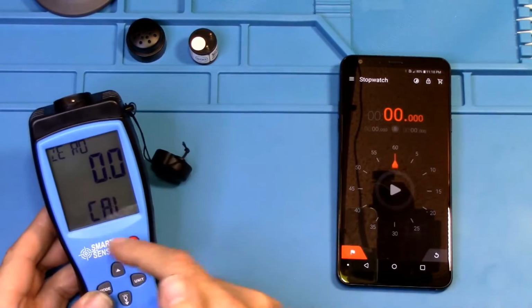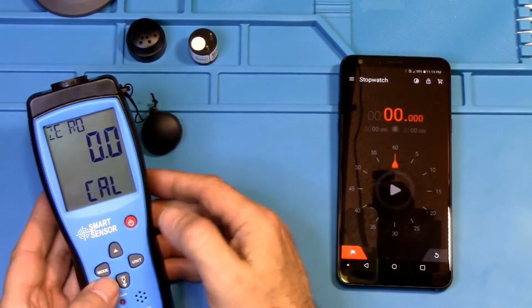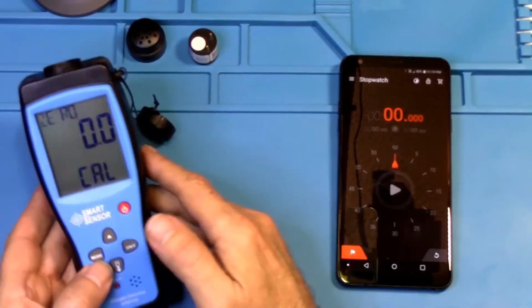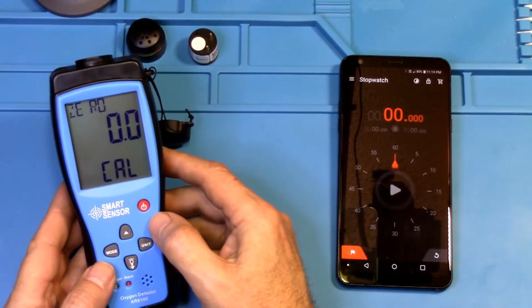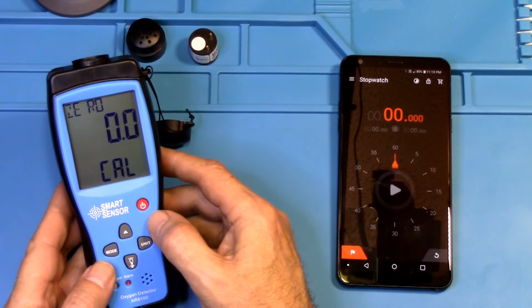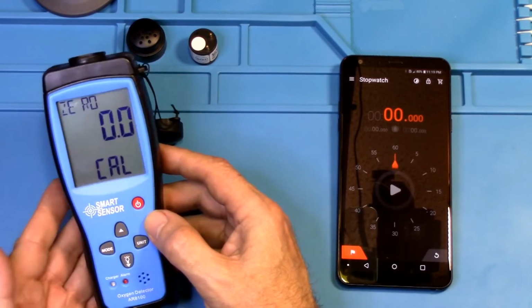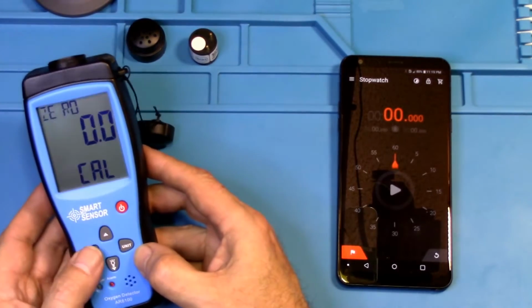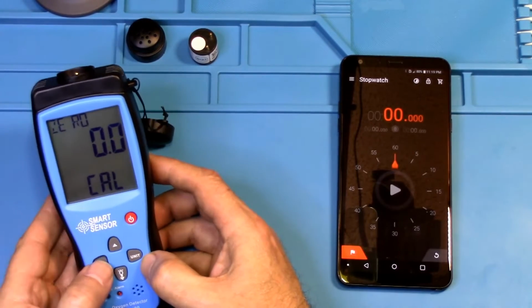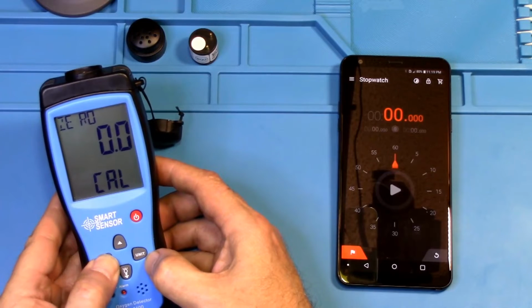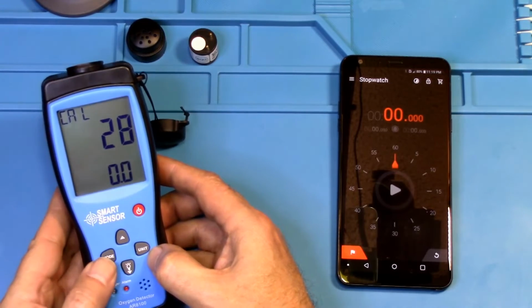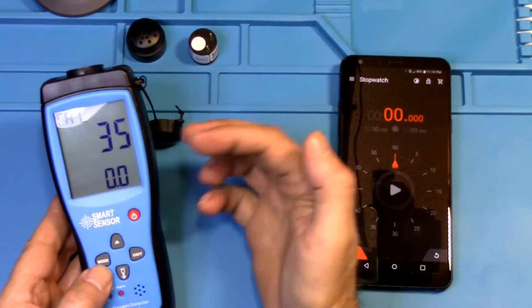Okay, 0, calibrate, CAL. Okay, so the next step is to press and hold the mode button for 3 to 5 seconds to enter the calibration mode. So this is the mode button, and press and hold it for a few seconds. Okay, there we are. Now we're at the calibration mode.